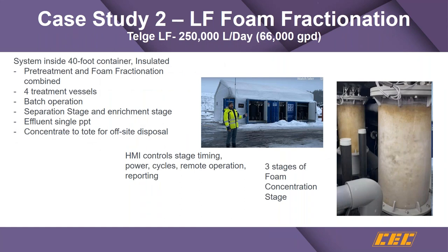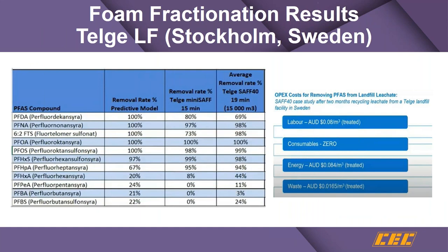Case 2 is another foam fractionation system at the Telge landfill, just outside Stockholm, Sweden — in a 40-foot container treating landfill leachate for over two years. Very little pretreatment is involved, just suspended solids removal like filtration, and they can obtain single parts per trillion of the sampled PFAS constituents. The regulated PFAS constituents achieve virtually 95 to 98 percent removals, while some shorter chain have much lower percentage removals. Importantly, treatment cost is much less than the equivalent of a cent per gallon, which is significantly cost-effective compared to other technologies.